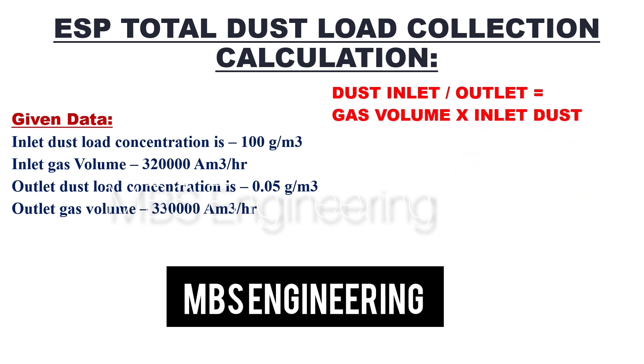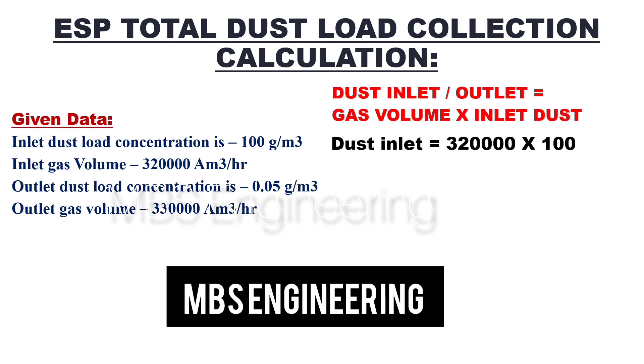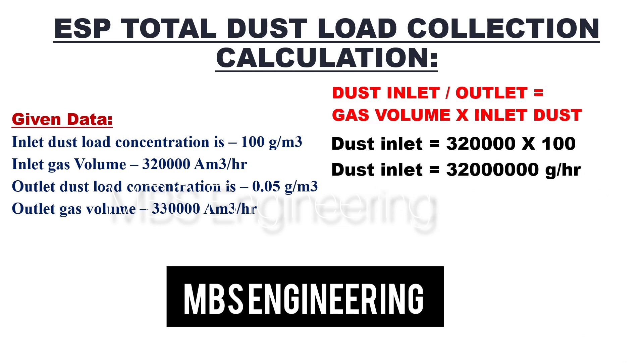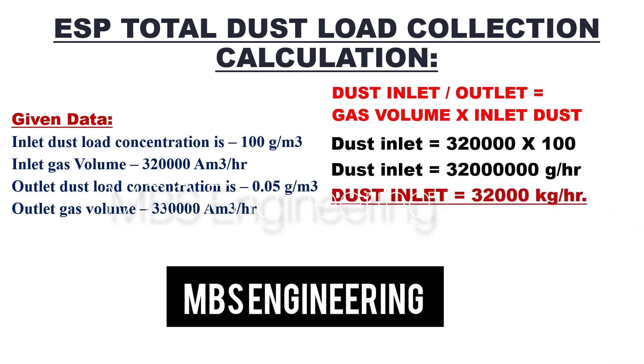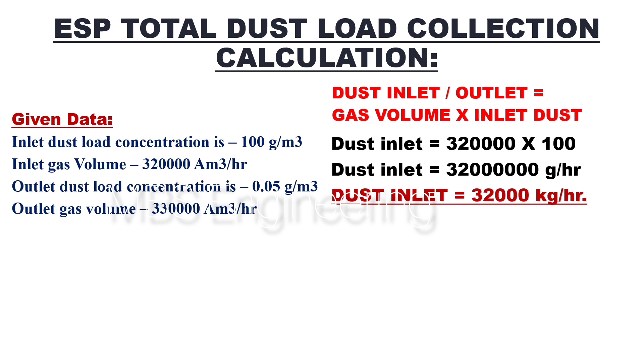Dust load is equal to gas volume multiplied by dust concentration. Gas inlet dust load equals 3,20,000 multiplied by 100, giving a dust inlet concentration of 32,000,000 grams per hour. To convert into kilograms per hour, 32,000,000 is divided by 1,000. The obtained inlet dust concentration value is 32,000 kilograms per hour.